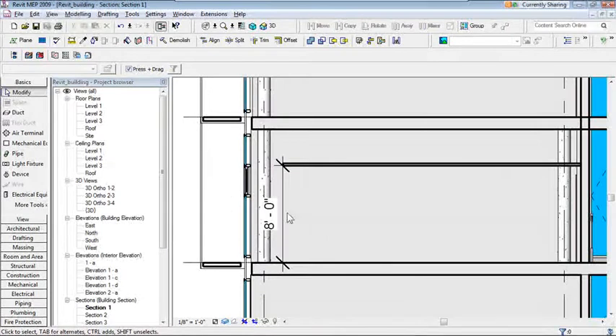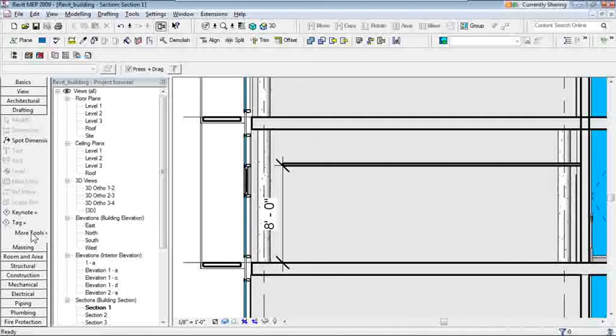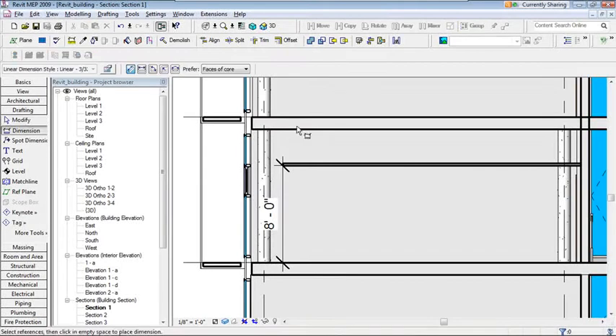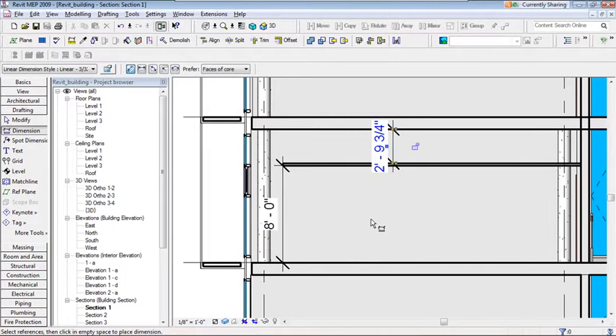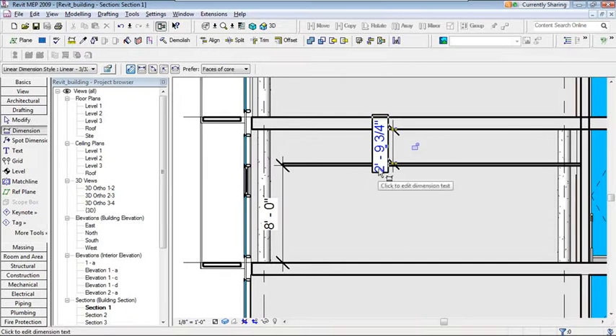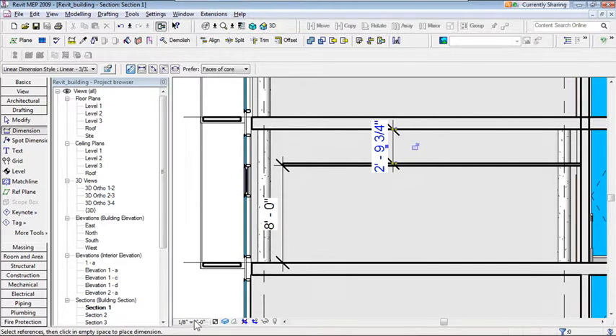I can click the dimension to make it permanent, so I know what elevation that ceiling is at. I can also go to Drafting tools in the Design Bar, select the Dimension tool, and dimension from the bottom of the floor to the top of the ceiling — giving me the available ceiling space. Then dimension from the top of the ceiling to the bottom of the structure: that shows two feet nine and three-quarters of an inch available to design in.